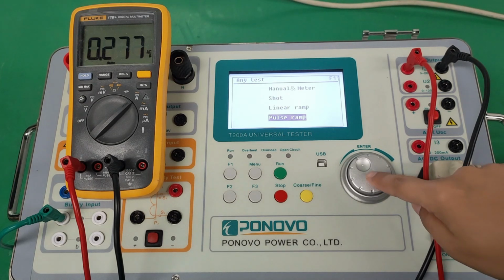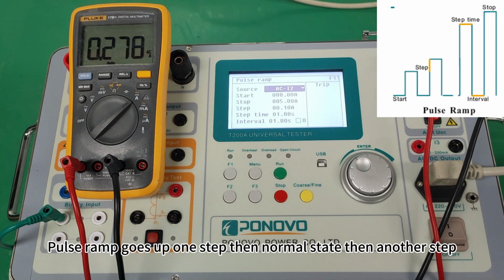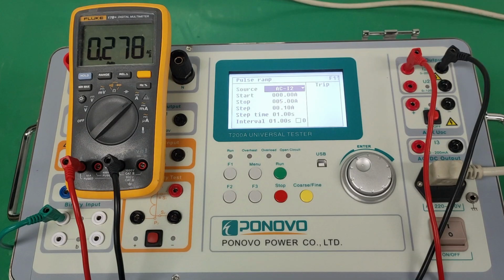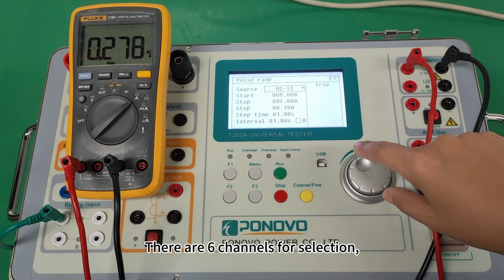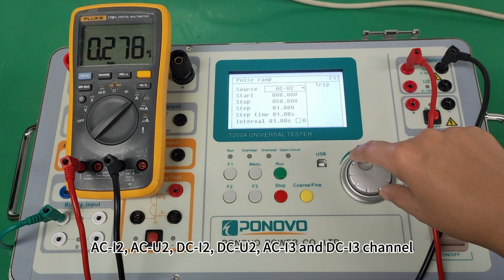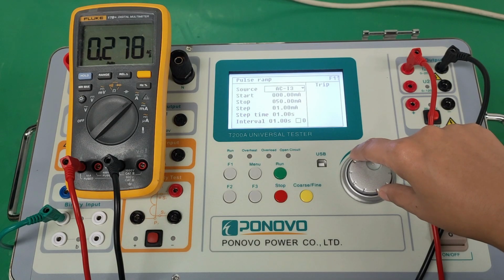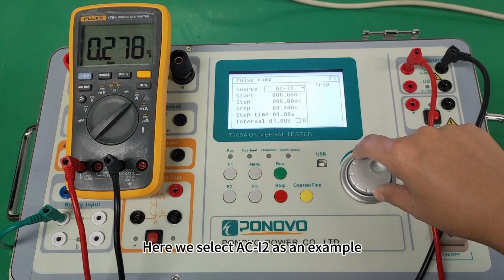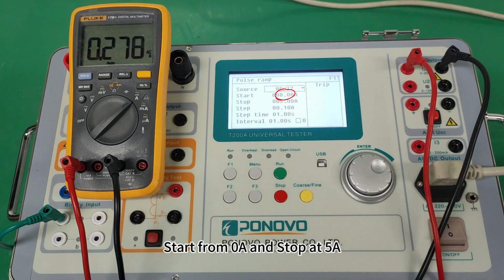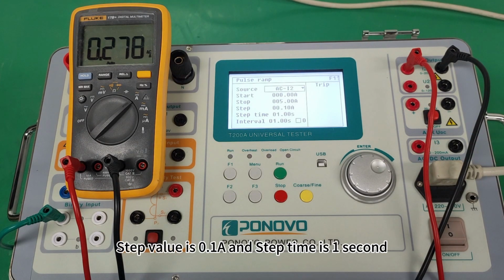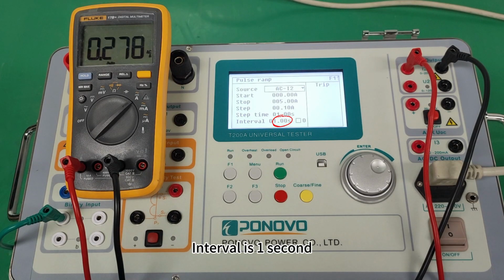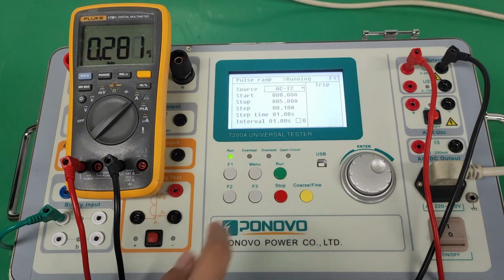Next, pulse ramp. Pulse ramp goes up 1 step, then normal state, then another step. There are 6 channels for selection: ACI2, ACU2, DCI2, DCU2, ACI3 and DCI3 channel. Here we select ACI2 as an example. Start from 0 ampere and stop at 5 amperes. Step value is 0.1 ampere and step time is 1 second. Interval is 1 second. Press run button.